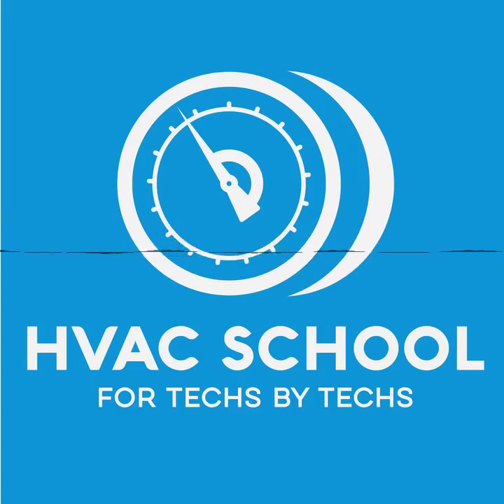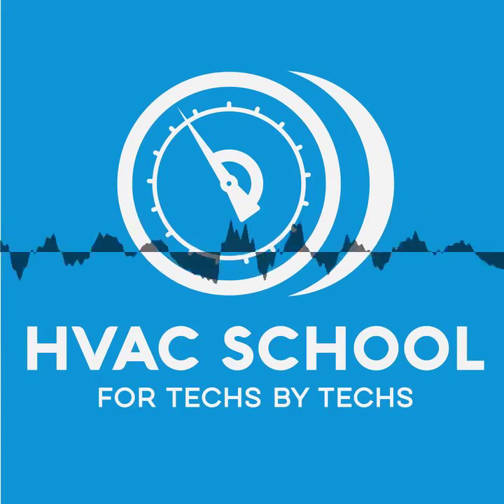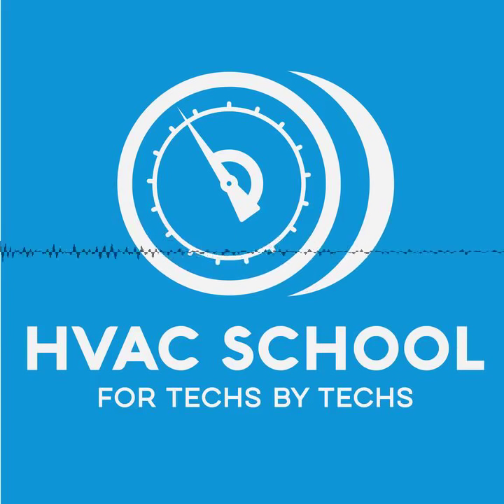So I like to try to tell people that no matter what you do to that dial, I even tell customers this, because a common service call is, I keep turning it colder and it's not getting any colder. We can also relate that to an air conditioning call at a residence too. But like I tell the customer, don't turn the dial, because that particular refrigerator has a constant cut-in control. So if it's not working, there's something wrong. Turning that dial really doesn't do anything. For us as technicians, we can tweak some things by turning that dial.